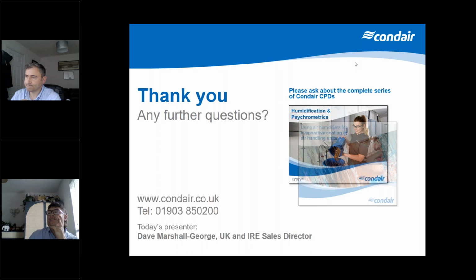Brilliant, thanks, Dave. The next question I have is, any suggestion on how to control the relative humidity when I do passive cooling through window opening? Well, it's really difficult actually to do. As soon as you do that, you are losing control of the environment, because your ambient relative humidity is going to be a direct reflection of the absolute moisture content of the air outside. So as soon as you do that, you might as well try and humidify the whole of the town that you're in. When people say I want to humidify a certain area, it's like trying to put a pile of water in a corner of a room. As soon as you let go, it spreads out, it dissipates.